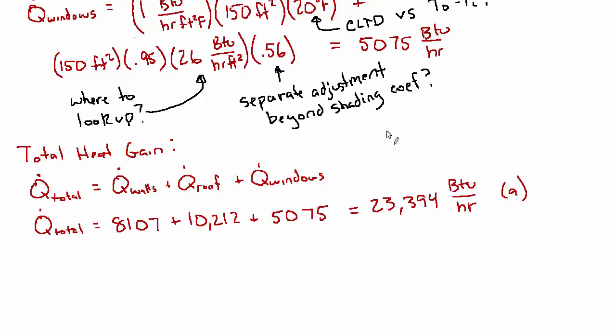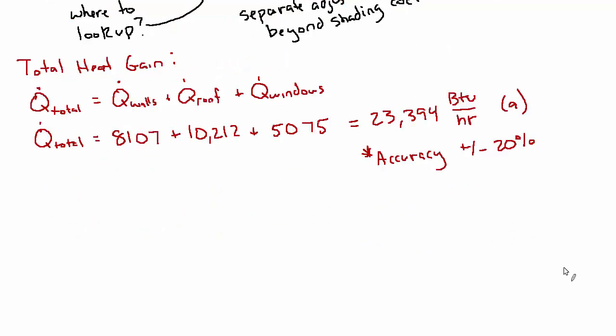And I really want to stress for this problem the accuracy here. There's got to be plus or minus 15 or 20% at best. There's so many assumptions. There's the lookup tables. There's the latitude. There's the properties of these materials. We're making assumptions for a lot of the materials. So from a design perspective, it's pretty important to be conservative here. So that you don't end up being unable to cool the space.